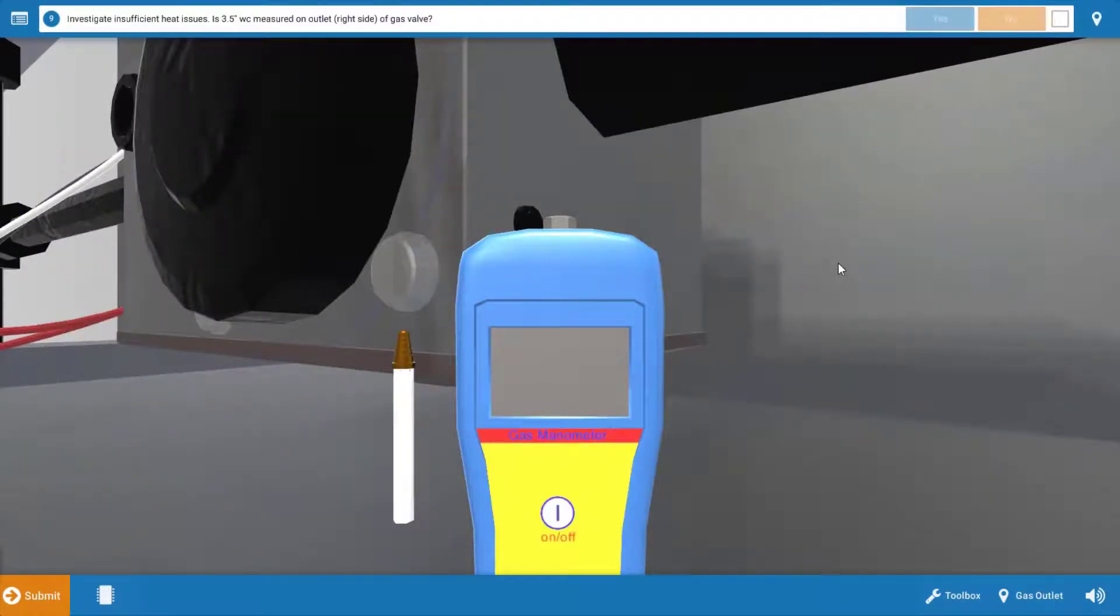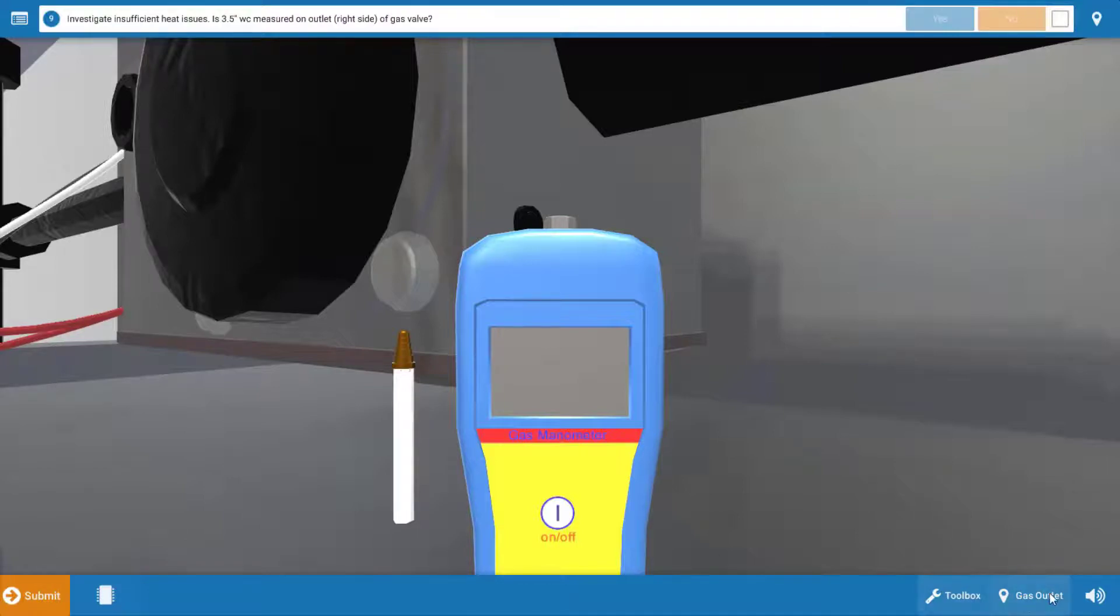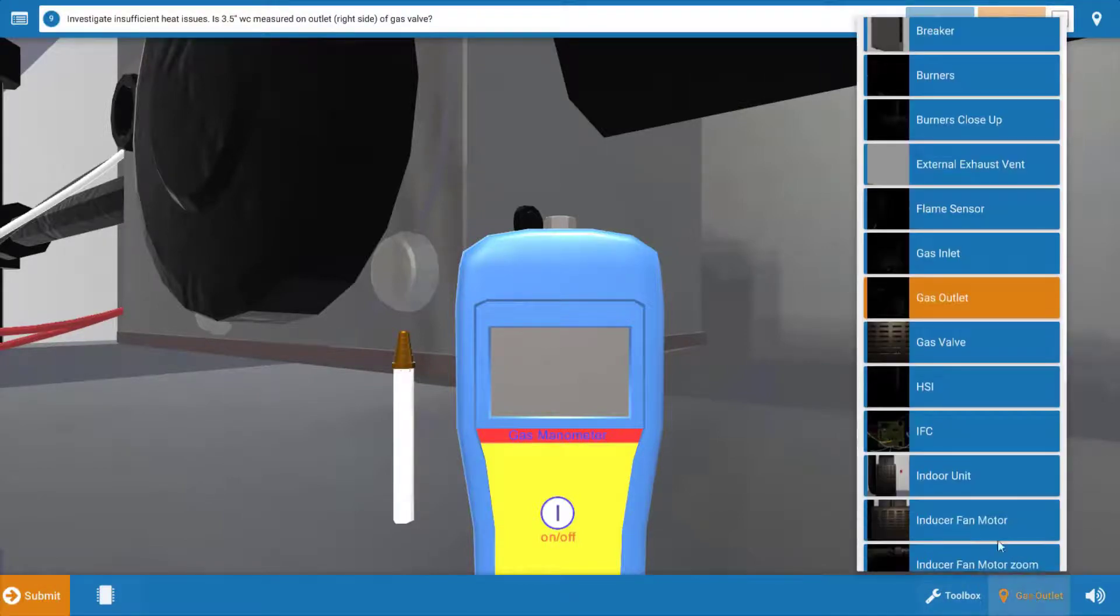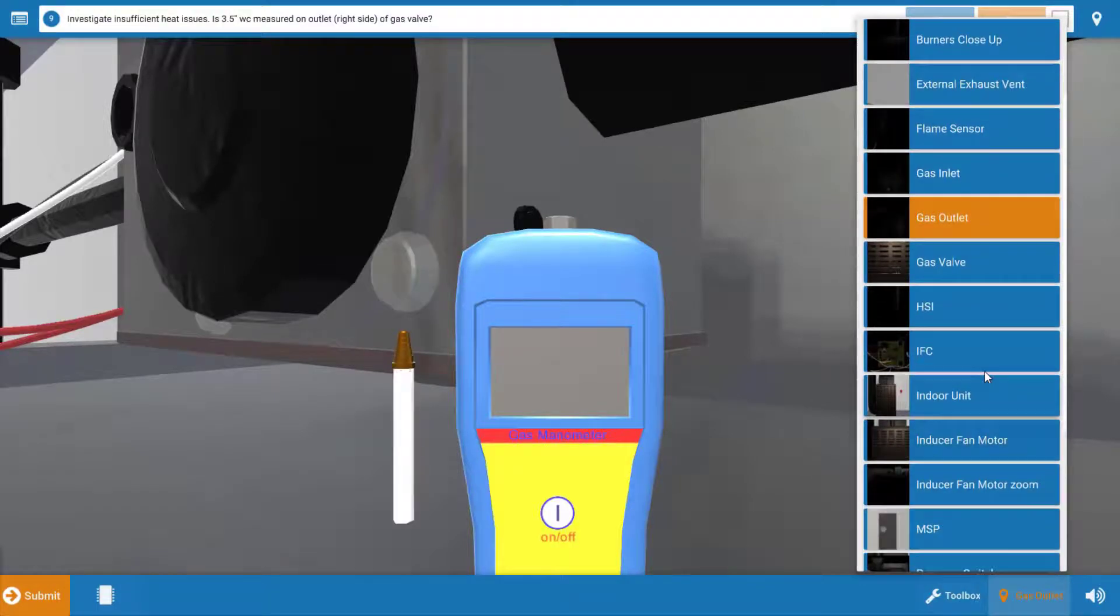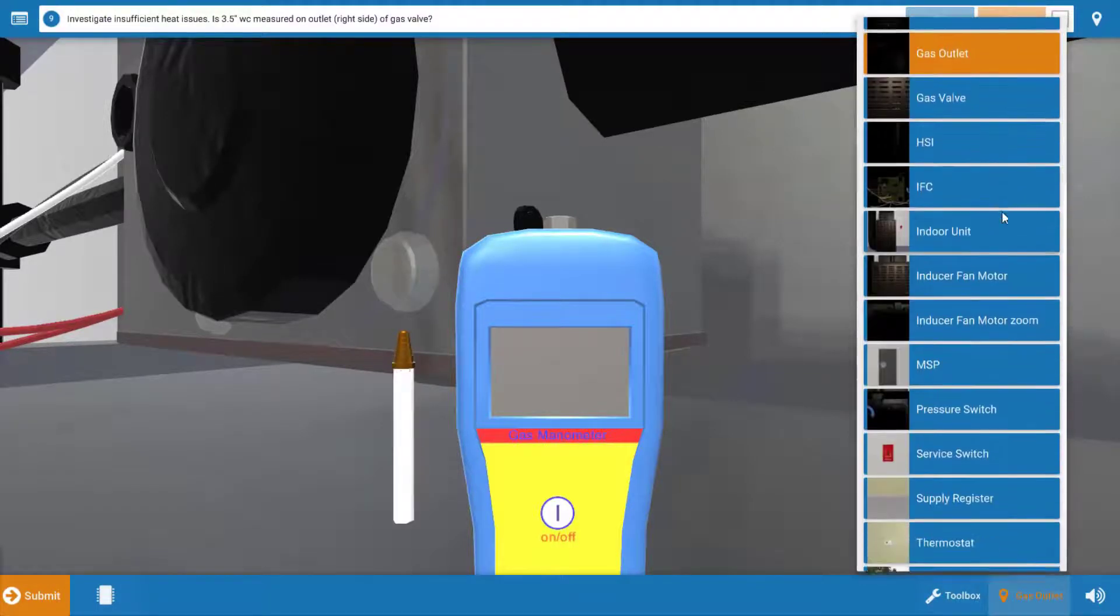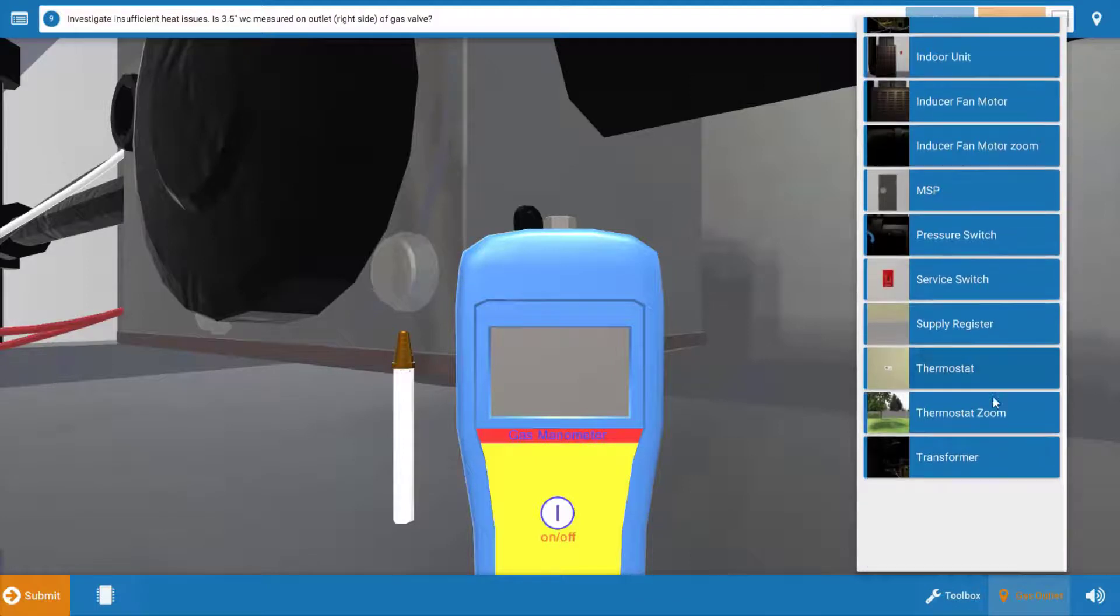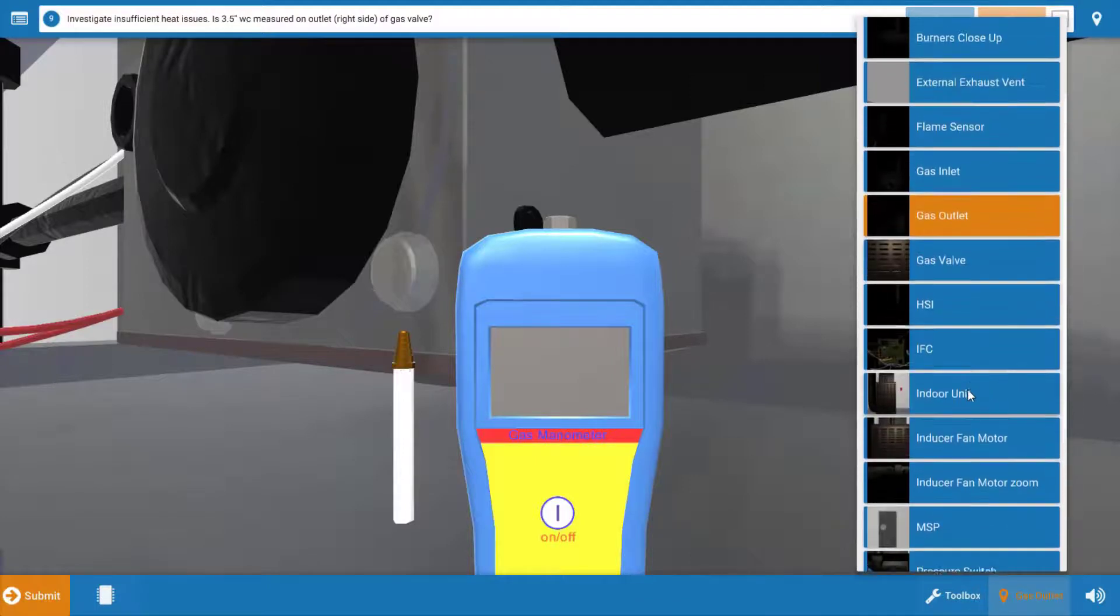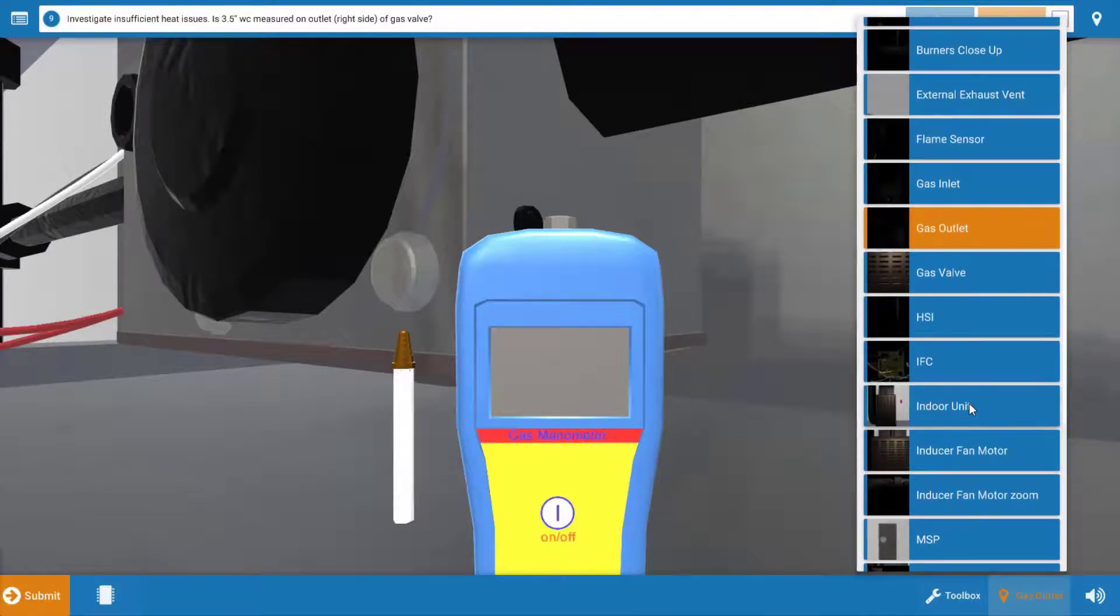Next, we're going to most likely have an issue with either fuel input here or possible restriction in the airflow. But before we actually measure gas pressure, click on this bottom right icon and we're going to teleport ourselves to the indoor fan motor just to make sure that the indoor fan motor is actually running.